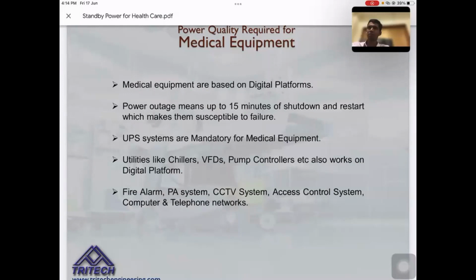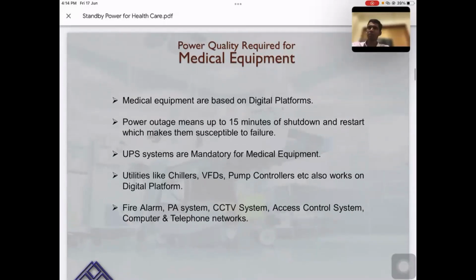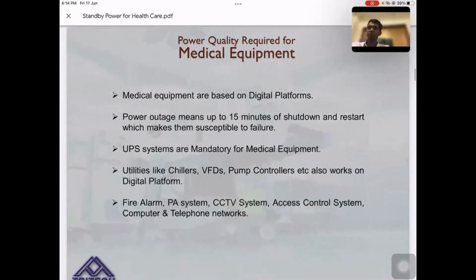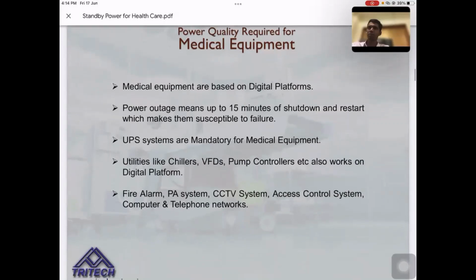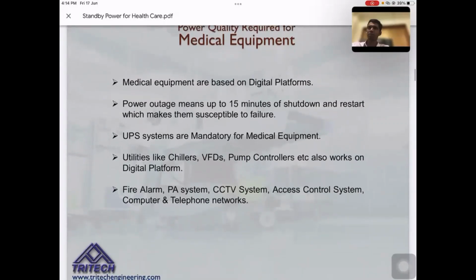Which means UPS systems are mandatory for all the medical equipment, most of the critical, large value medical equipment. And again, many of the utilities like chillers, VFDs, pump controllers also have the digital platform, which is microprocessors. So they also these days are very sensitive to power outages. If you look at the other services like fire alarm, PA system, CCTV, access control, telephone and computer network, these are also critical utilities which work on the digital platform.